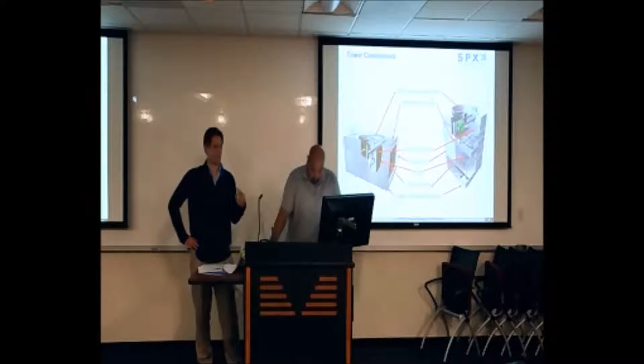What's the lead time on a 75 horsepower motor? Lead time, if Baldor has them in stock, or if you want it from Marley, Marley has them in stock. Just keep in mind, Marley uses a severe duty motor, so if you're going to replace it with something else, make sure it's like for like. I know a lot of guys replace them with Baldor motors, premium efficiency TEFC, but that may not be the proper motor because of the amount of moisture and humidity in there. It may fail prematurely. It may last you 5 years, but Marley does use a severe duty motor, so just keep that in mind.